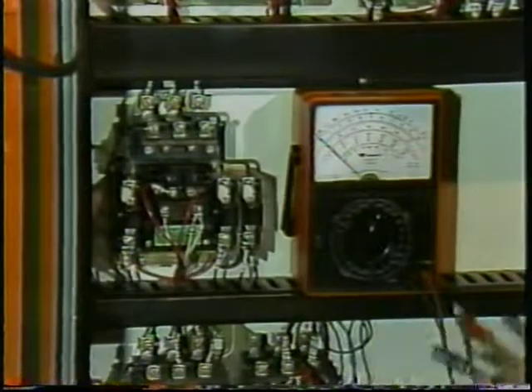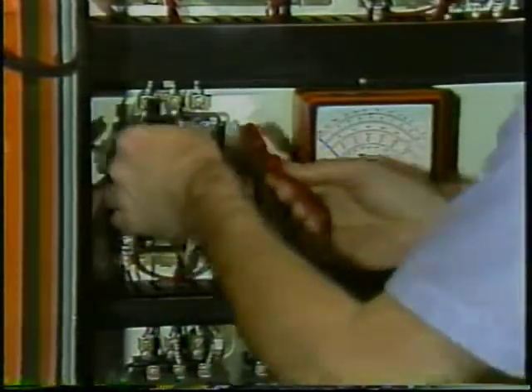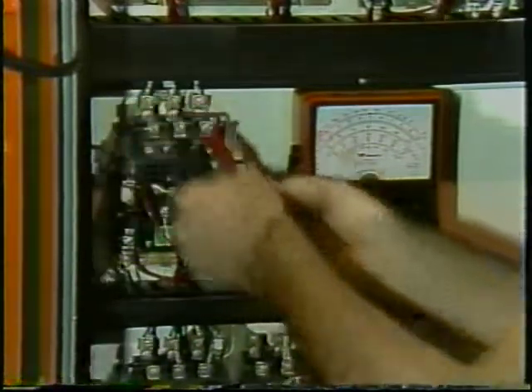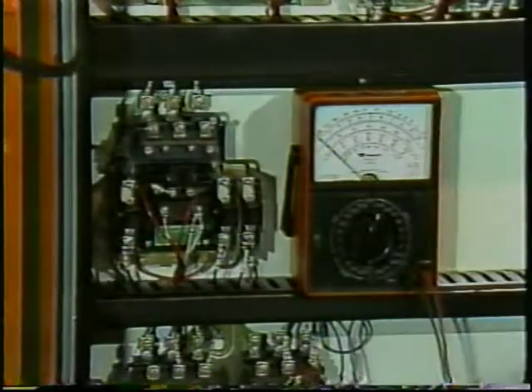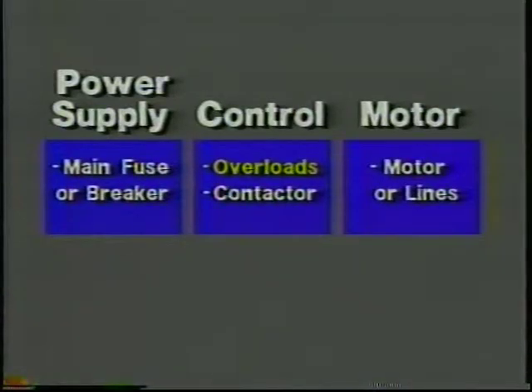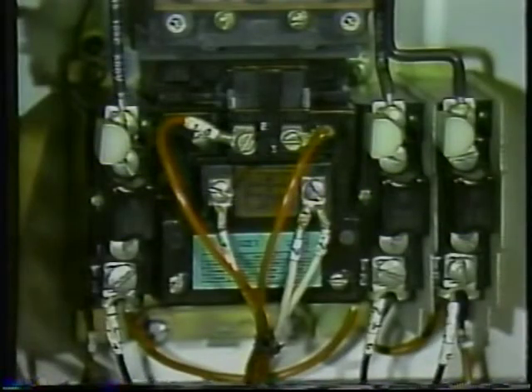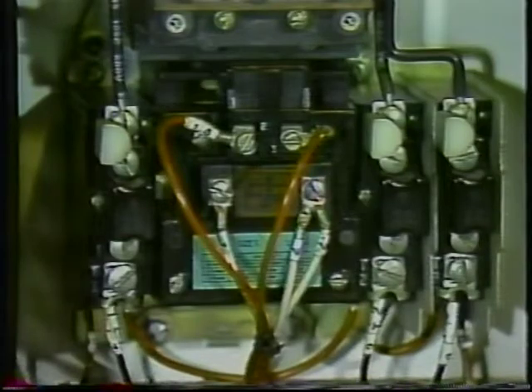Probably a tripped breaker or blown power line fuse. To eliminate these, you would take a voltage reading to see whether power is reaching the contactor. With an open in the motor, you would find normal voltage. This eliminates the main fuses or circuit breakers and everything else that brings power to the starter. Next, you try to eliminate the contactor and control circuit. See whether the contactor pulls in when the start button is pushed. In this case, it would.